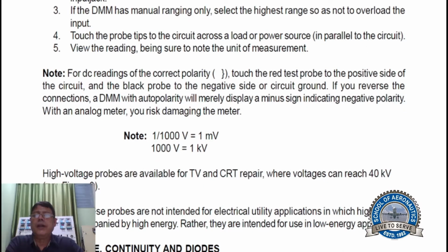Note, for DC readings of the correct polarity, touch the red test probe to the positive side of the circuit and the black probe to the negative side of the circuit or ground. If you reverse the connection, a DMM with autopolarity will display the minus sign indicating negative polarity. With an analog meter, you risk damaging the meter.